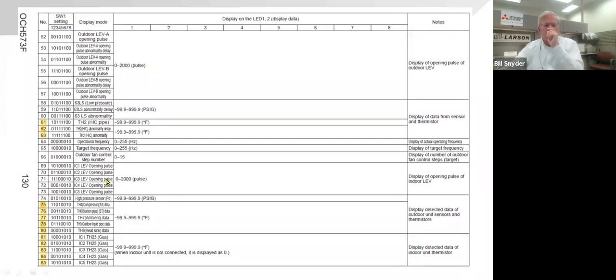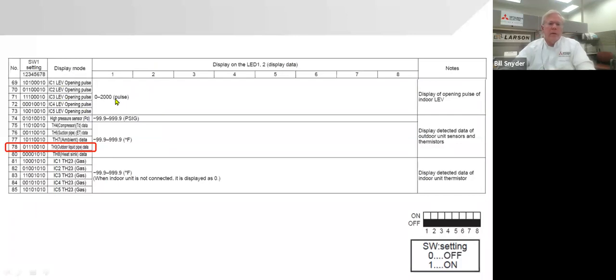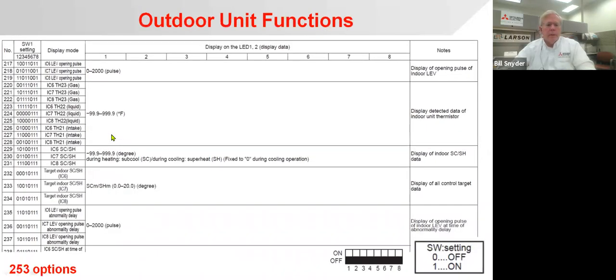And you can see on here the LEV opening, how many pulses it's opened, what the high pressure temperature sensor coming off that compressor is reading. There are literally 253 options here that you can look at. It even gives you your target superheat if you switch those switches to the right position.